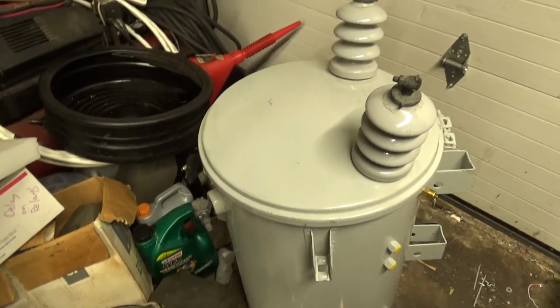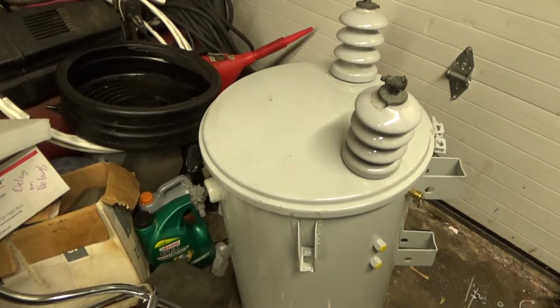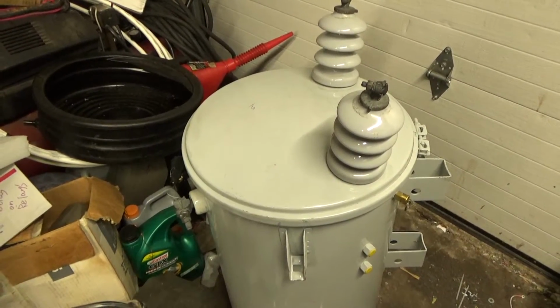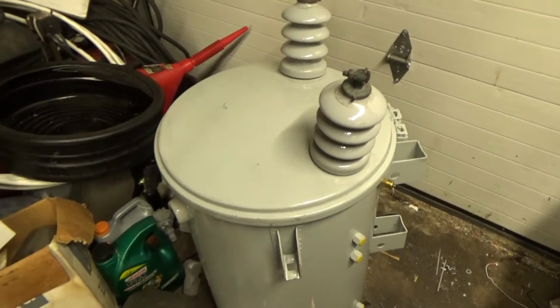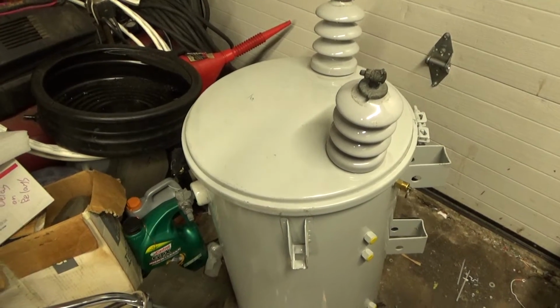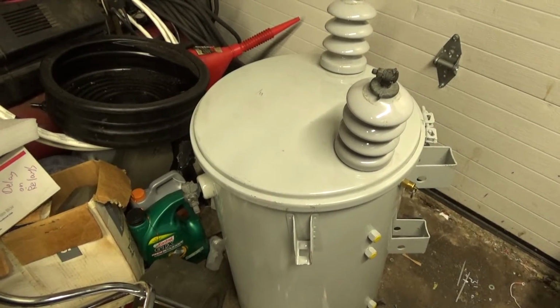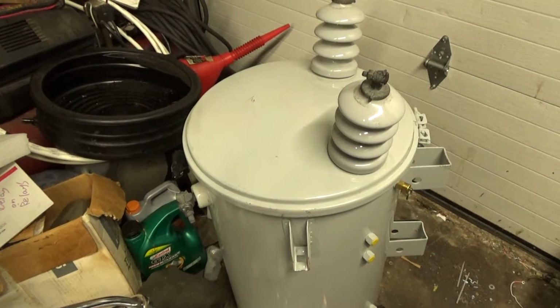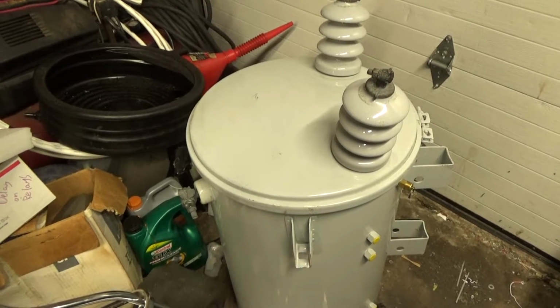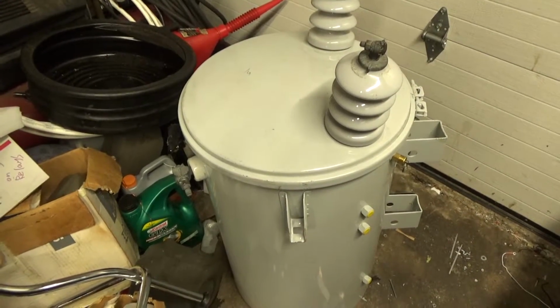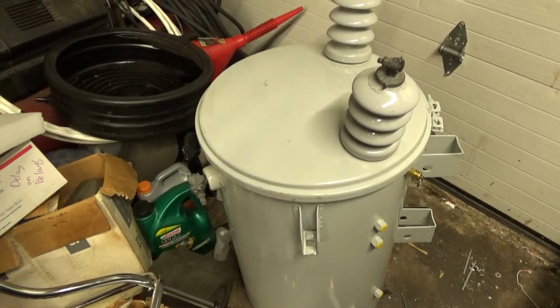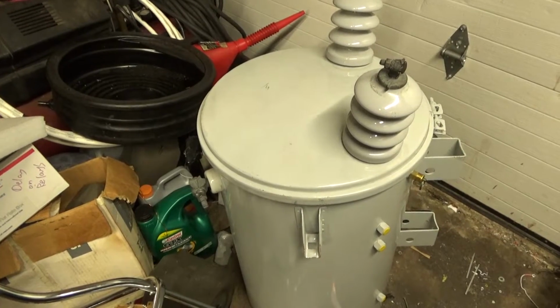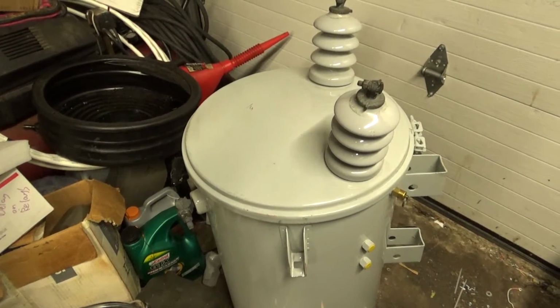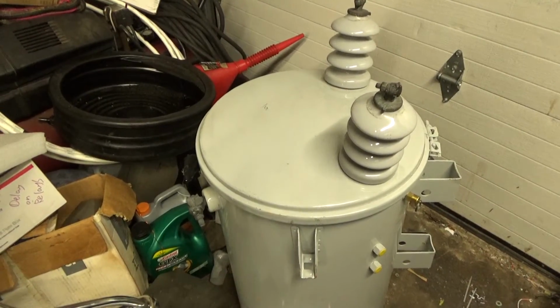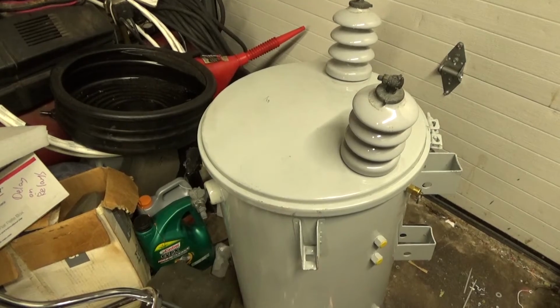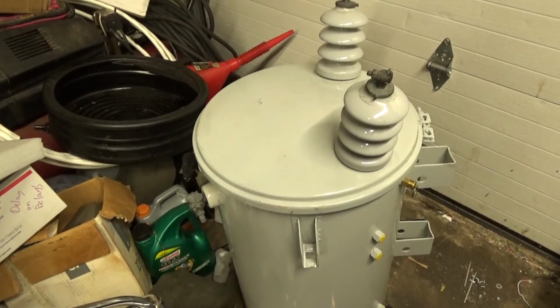The oil not only cools the core, but it's absorbed by the insulating material between the windings, which isn't the same as a conventional transformer. So once all of the oil is gone, even if you're running the transformer at a lower power level, so you're not trying to suck the max kVA rating out of it, eventually they always end up flashing. It heats up, then the enamel wire, the coating on the wire, breaks down, and they flash. They're just not designed to be out of oil.